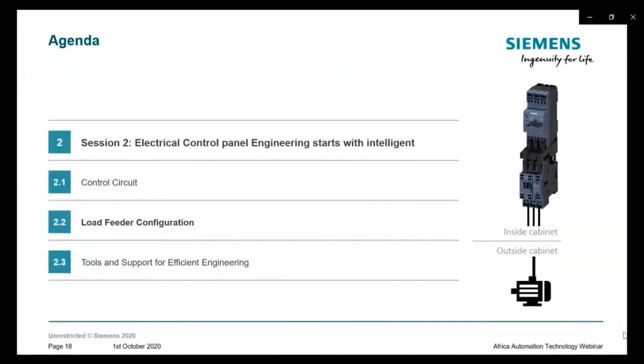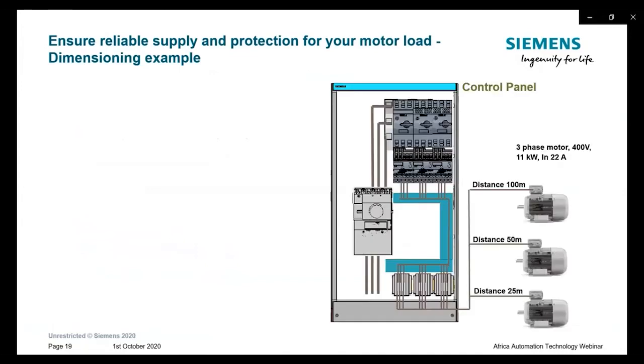Let's go now into the load feeder configuration, including the conductor dimensioning inside the cabinet and of course outside the cabinet. Ensure reliable supply and protection for your motor load. So let's go into a dimensioning example. Here's an example for the machine with a control panel and 3 motor loads, all connected to 400 volt systems.